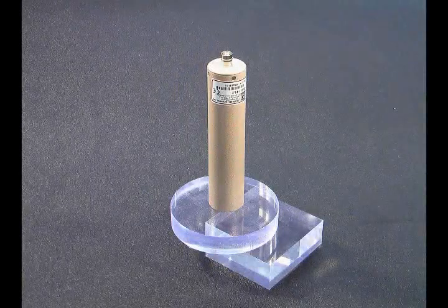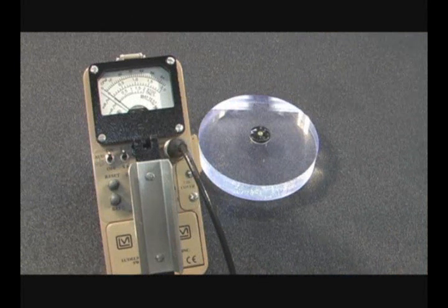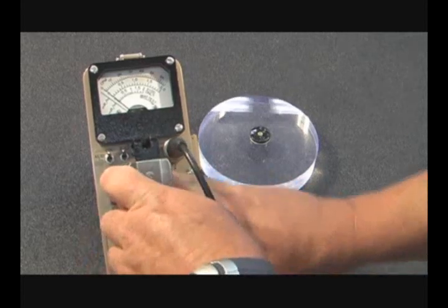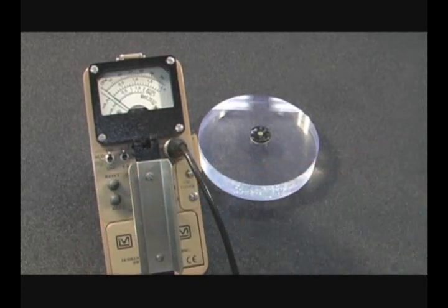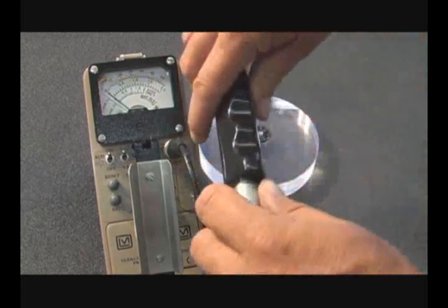Now let's change over to the Model 44-2 gamma detector. Remember that the Model 44-2 will only detect gamma radiation. Turn the range selector switch to the off position to prevent electrical shocks in the internal pin of the cable. Disconnect the Model 44-9 and replace with the Model 44-2 detector using the same cable.